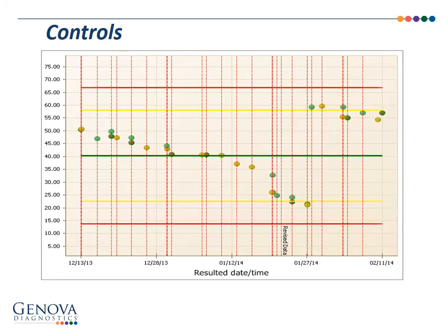CVs, again, can't just be used on their own. You have to be looking at them as part of the larger picture. So in this case, for example, if I were to just look at the mean and the CV of this running control, it would look like everything is perfectly fine. Mean is right on, the CV is right on, but clearly there's something going on with this control, right? So supervisors, when they're watching their controls, are not just looking at the numbers, they're also looking at how are they behaving? Are they trending? Are they dropping? Have they shifted? In this case, clearly they have dropped.